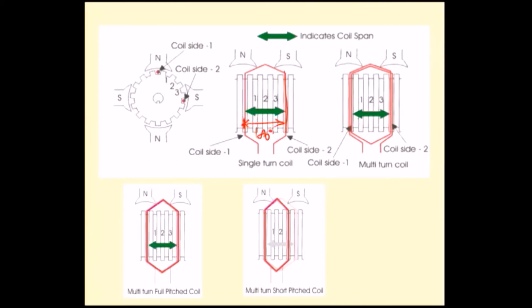Full pitch means the first slot to the 10th slot. In our example, slot per pole is 10 (20 divided by 2). This means the first slot and the other side of the coil should go through the 10th slot. If the other side is placed in the 9th slot, that is called short pitch.